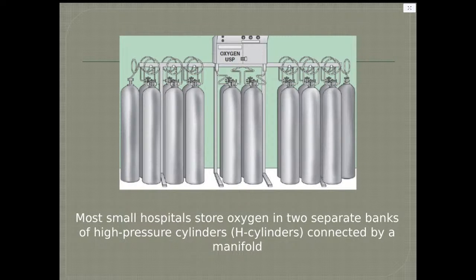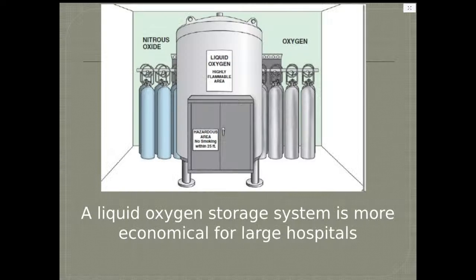Here you see in the picture oxygen hospital cylinders. Most small hospitals store oxygen in two separate banks of high pressure cylinders, each cylinder connected by a manifold.